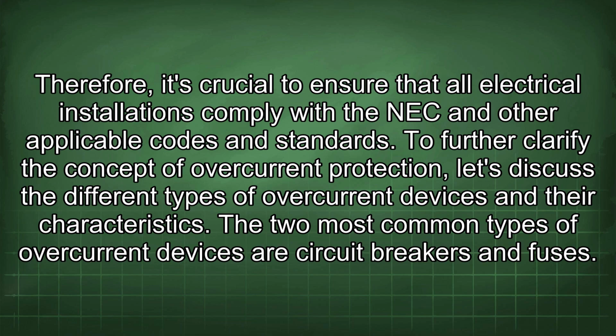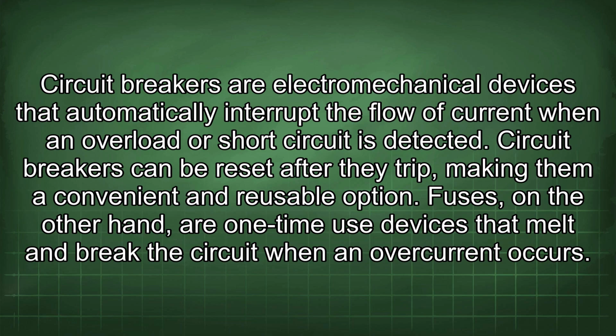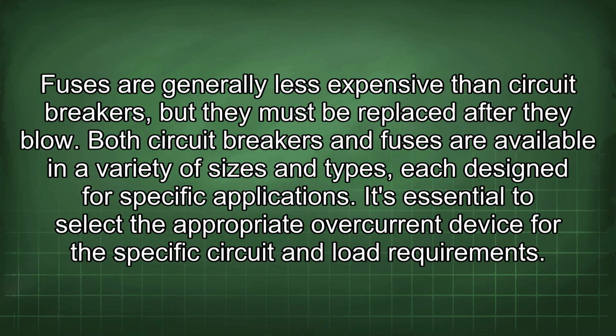To further clarify the concept of overcurrent protection, let's discuss the different types of overcurrent devices and their characteristics. The two most common types of overcurrent devices are circuit breakers and fuses. Circuit breakers are electromechanical devices that automatically interrupt the flow of current when an overload or short circuit is detected. Circuit breakers can be reset after they trip, making them a convenient and reusable option. Fuses, on the other hand, are one-time use devices that melt and break the circuit when an overcurrent occurs. Fuses are generally less expensive than circuit breakers, but they must be replaced after they blow. Both circuit breakers and fuses are available in a variety of sizes and types, each designed for specific applications. It's essential to select the appropriate overcurrent device for the specific circuit and load requirements.